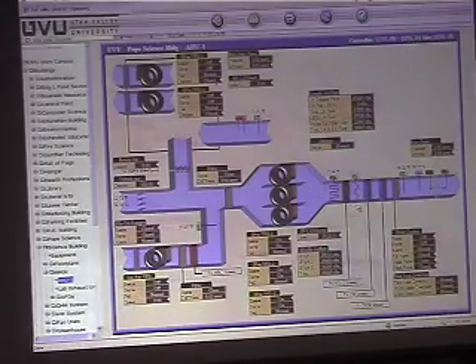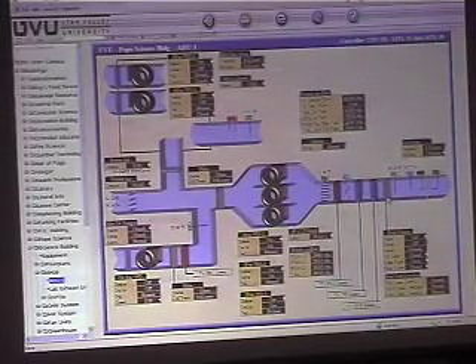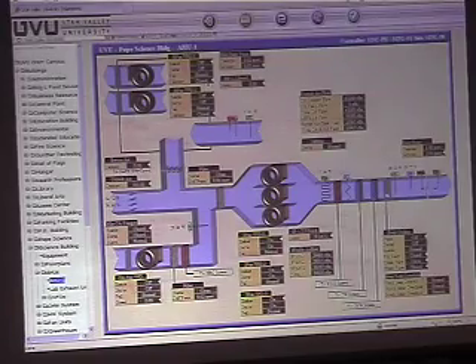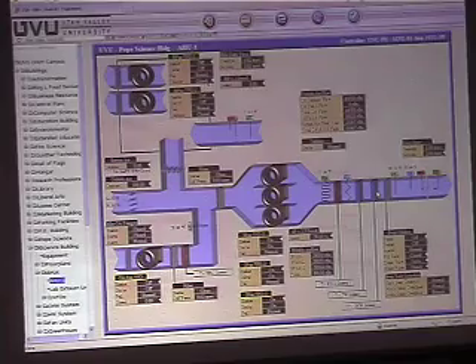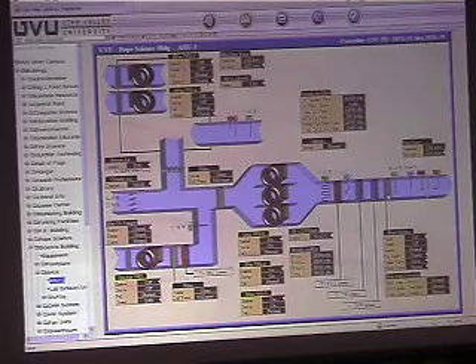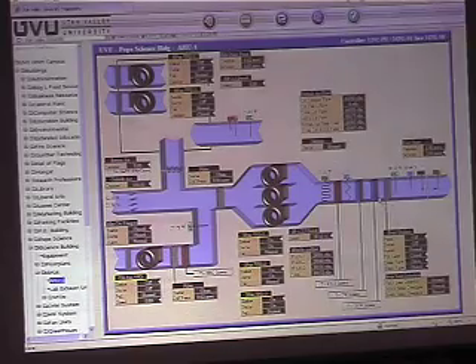So we go back to the air handler here. Your next stage is actually evap, even though obviously the evap has to be after the chilled water coil, or all it'll do is condense all your water out of the air and you lose your cooling. But yeah, the next stage after the indirect cooling is your direct cooling. So the equipment for this one is represented here.